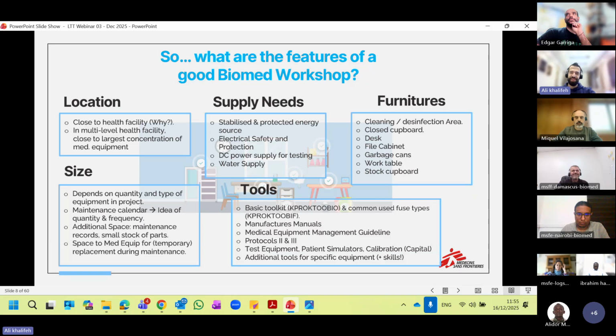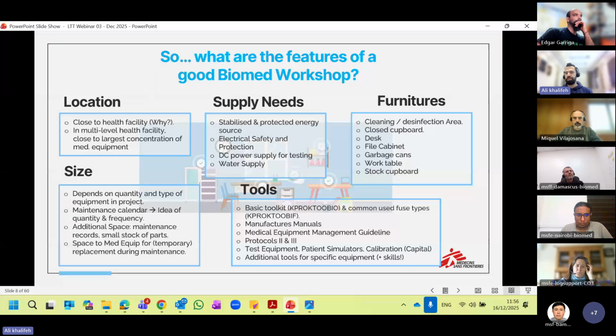If possible, yes, for many reasons. Biomed equipment is usually used directly with patients. They have bacterial filters, antibacterial filters. You remove the dust sometimes, so the risk of infection spread by the biomedical equipment is very high. Even if they are doing protocol cleaning from outside, whenever you do maintenance, you open the machine from inside, removing particles, dust, removing some parts. We have some breathing circuits, some filters. For this, we always recommend having a dedicated biomedical workshop only for biomed with very high IPC measures, like a disinfection cleaning area, and not to open the machine and spread whatever we have from the machine inside the hospital or inside the medical department.